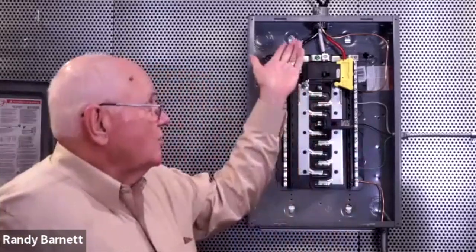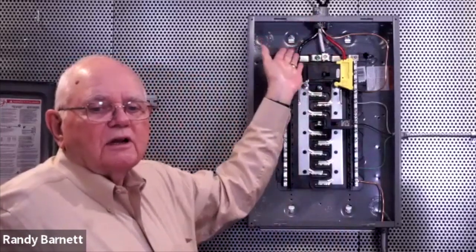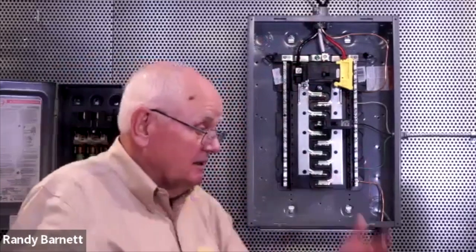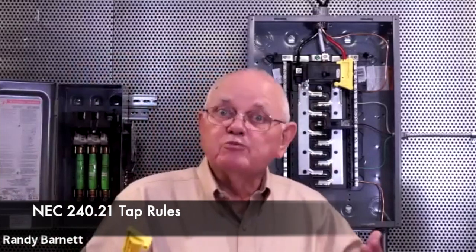So if these are tap conductors coming from a transformer, secondary tap conductors from the transformer coming on into this panel, then yeah, I've got to have those barriers in place as well. Why? Well, because I have to go upstream on the primary side to de-energize the transformer. So once again, similar to a service, we have to have the barriers in place if we're tapping secondary taps off a transformer. Now, the same is true in Article 240, overcurrent protection, of the NEC. We have 240.21, which is our tap rules.